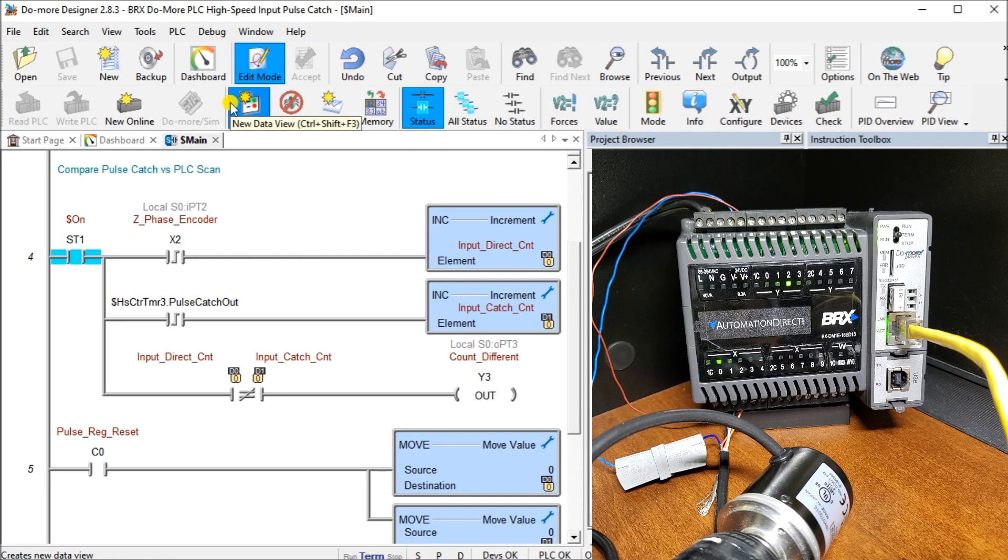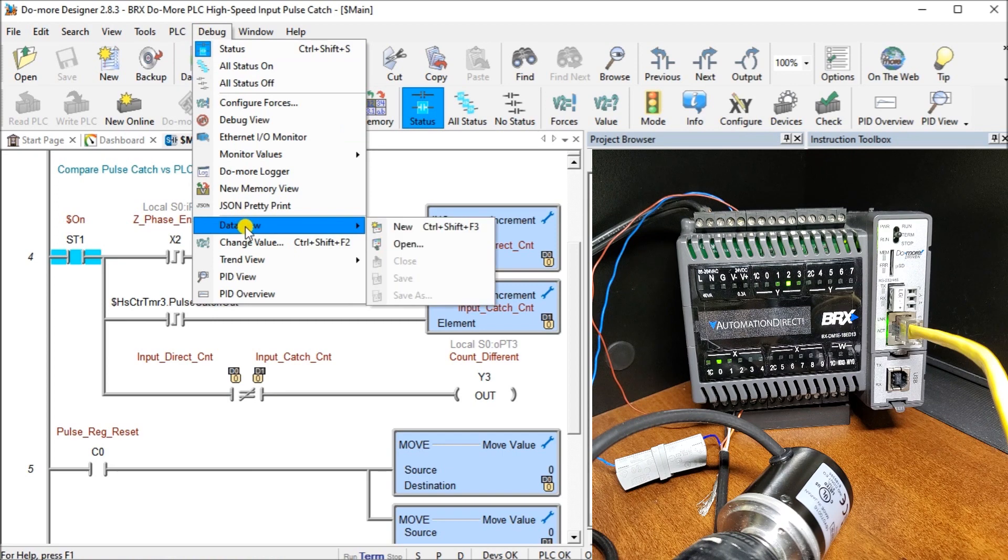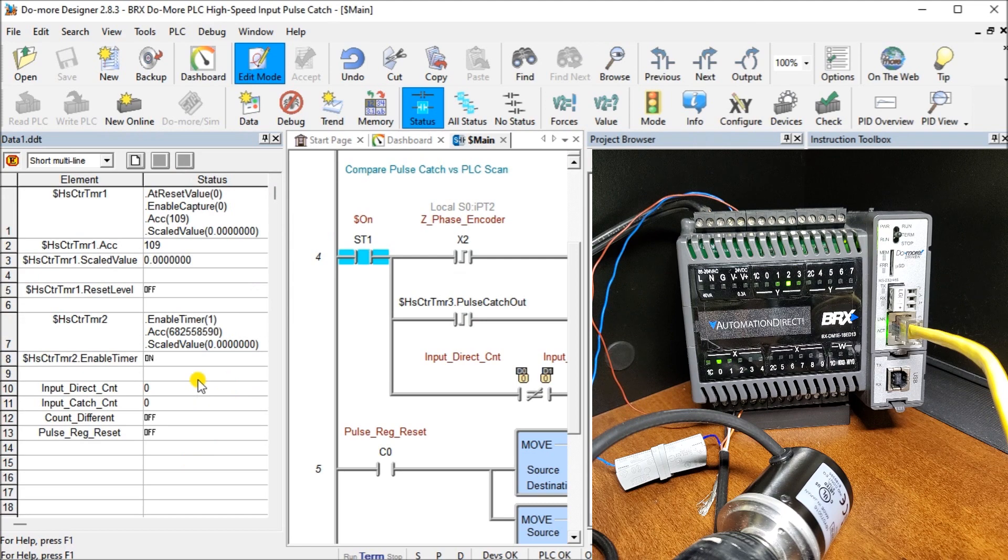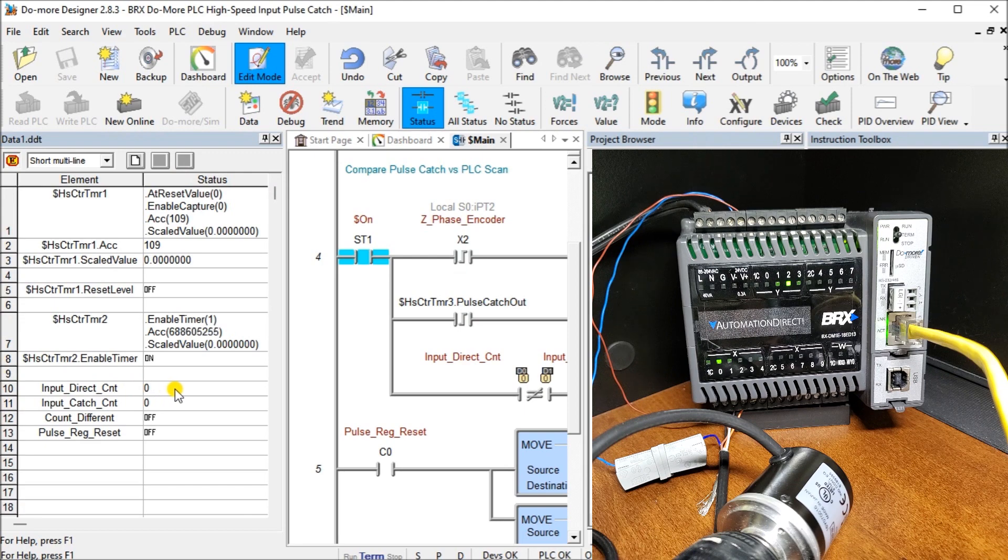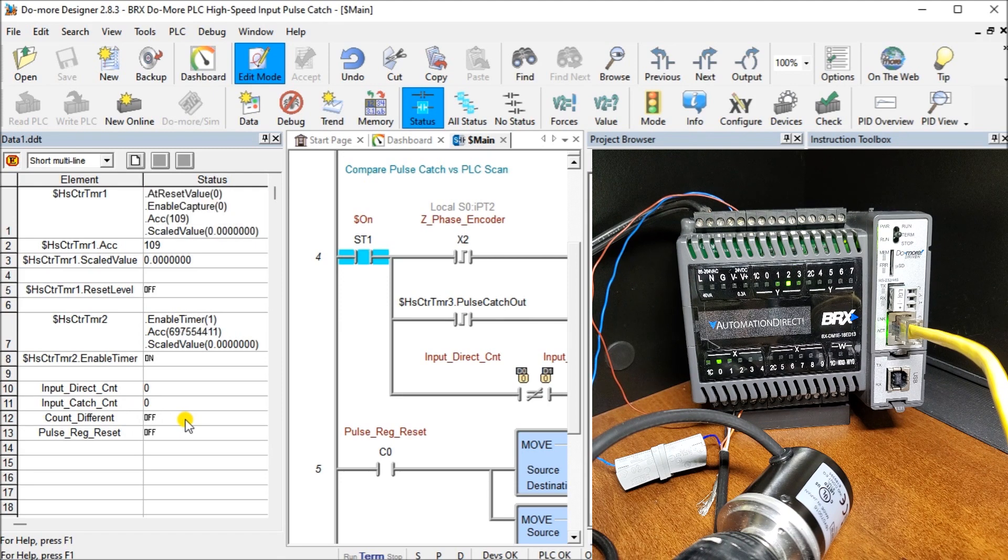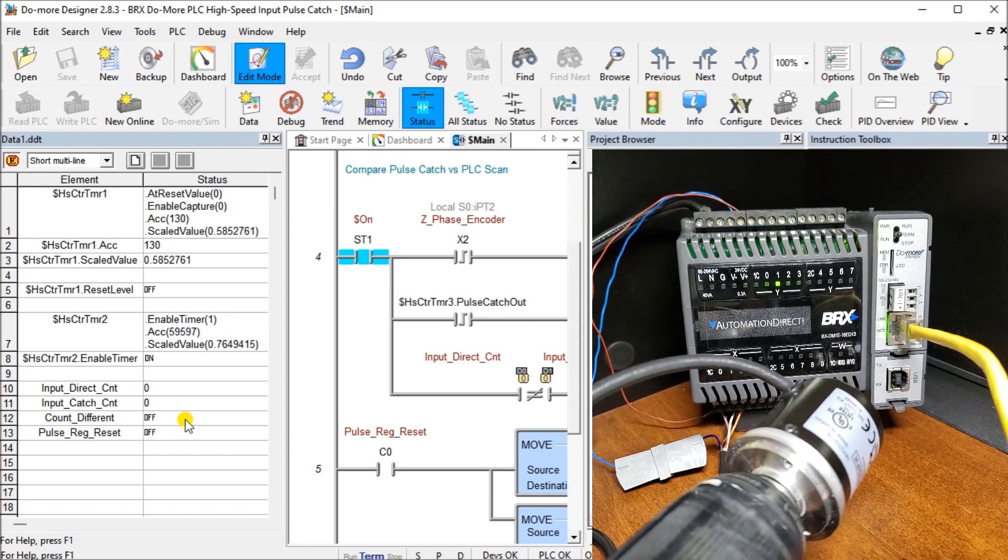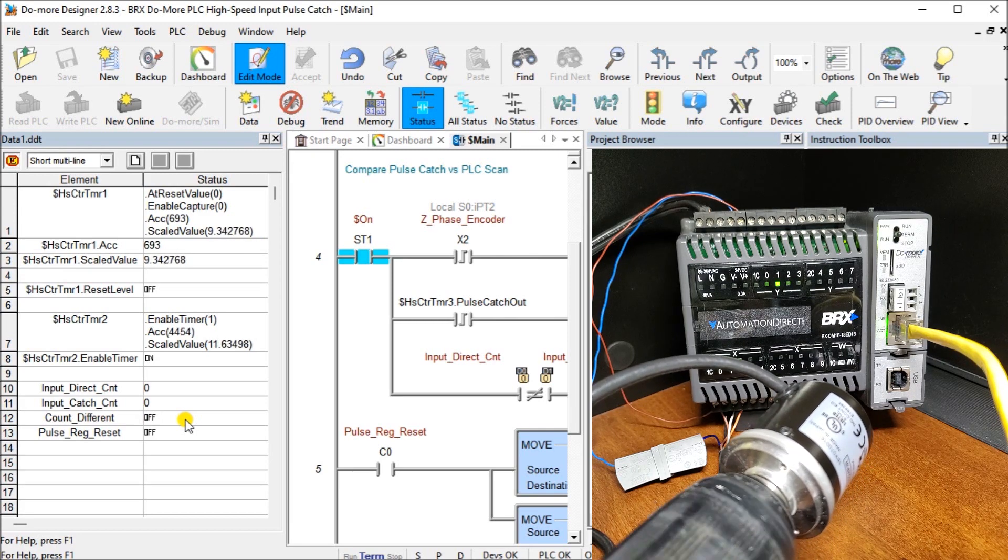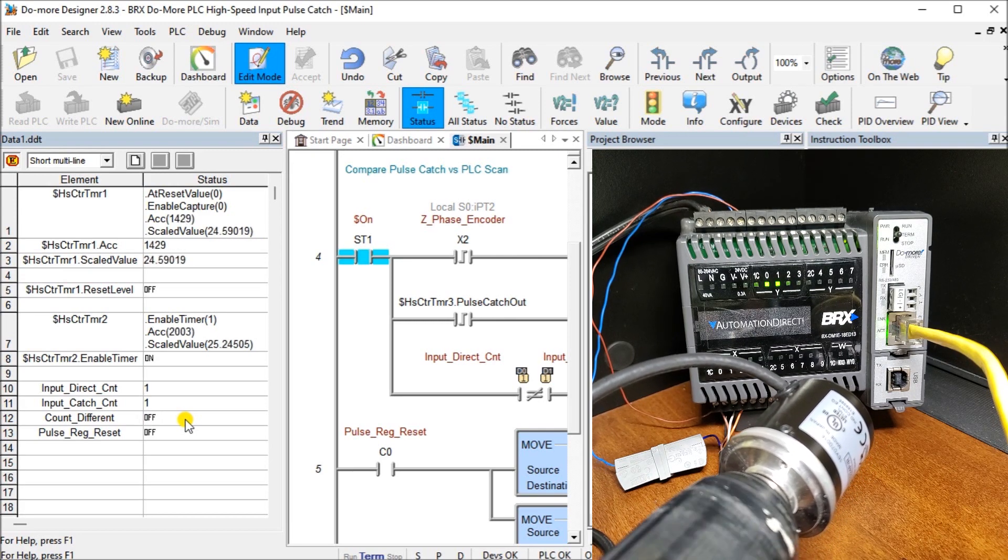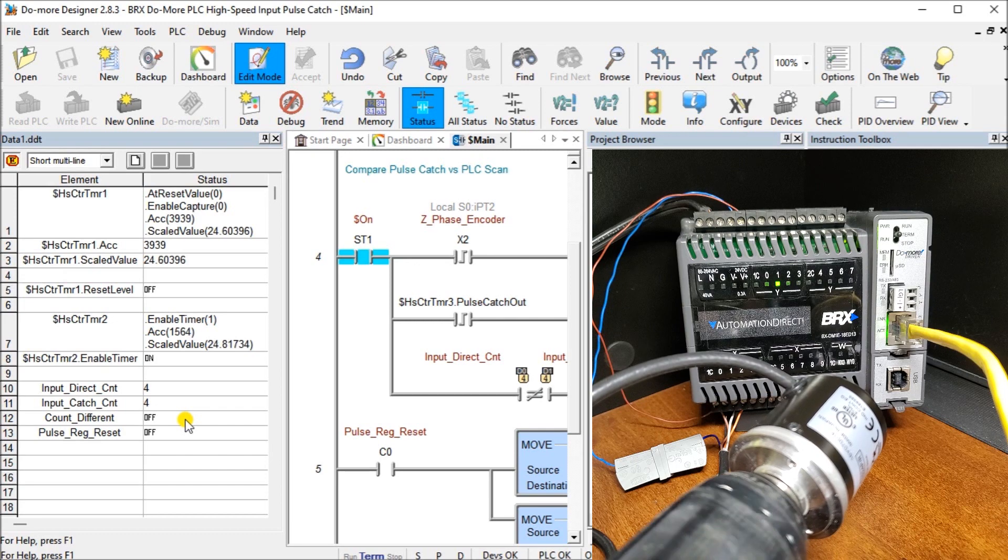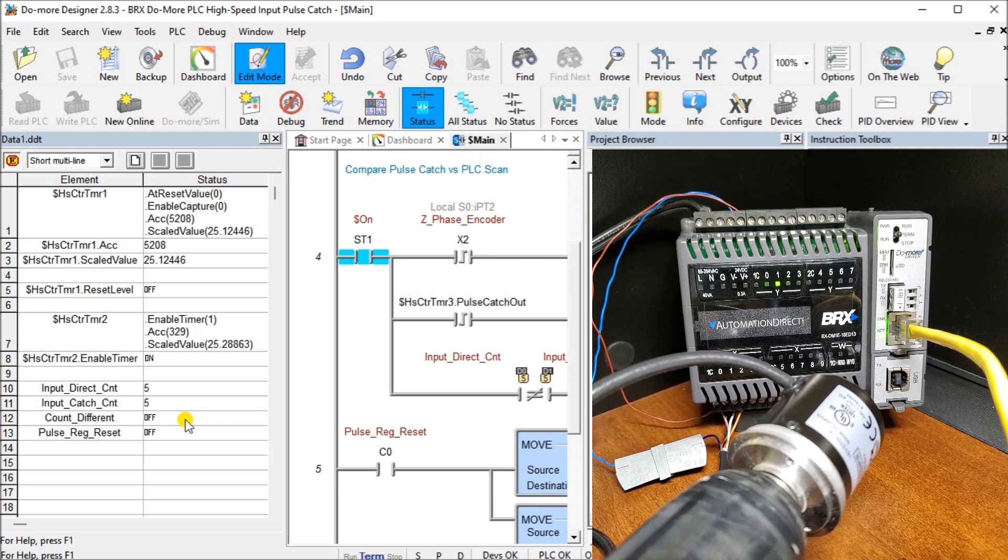Let's take a look at our data view. Our data view is going to show us the actual inputs. Here's my direct count input, so this is directly from the PLC scan. This is my input catch, and this is my difference, whether that Y3 is actually on. I have my encoder attached to a drill, so I'll start spinning it. We'll go slow at first. And what you'll notice is that we count one, and they're both all the same. Speed up a little bit here. Two, and three, which is all good if we're within a speed.